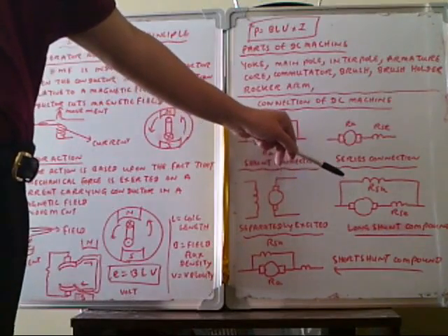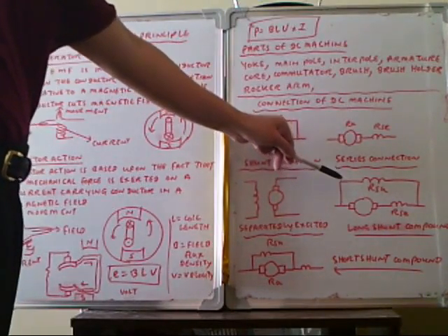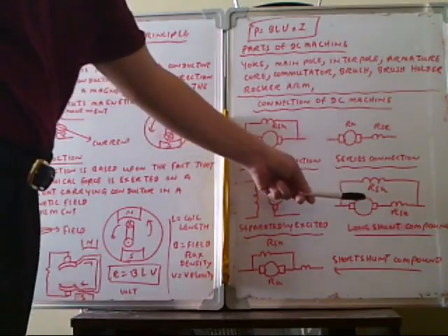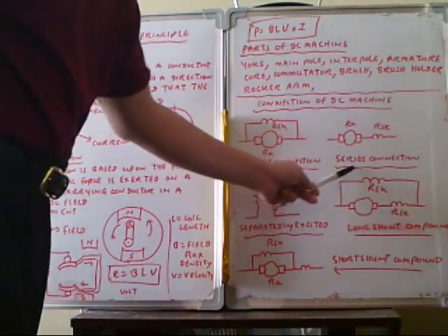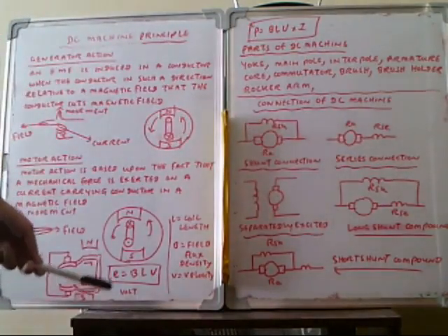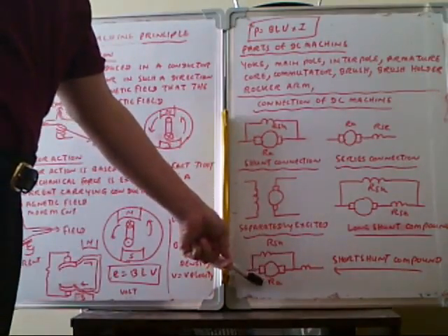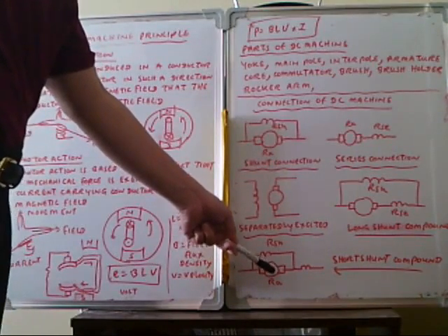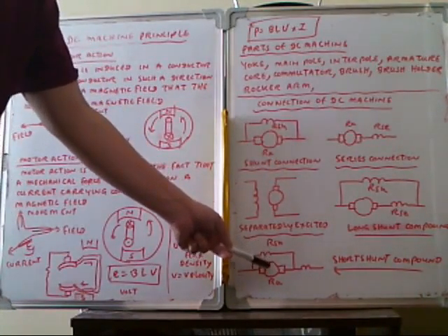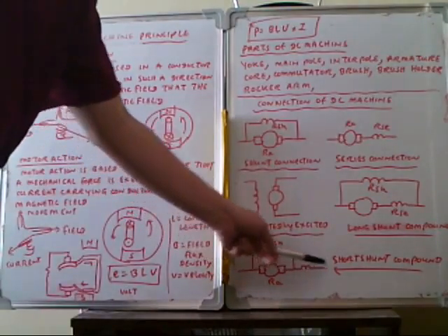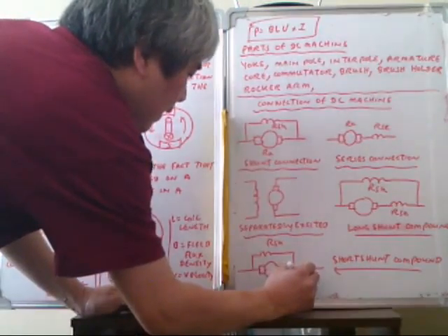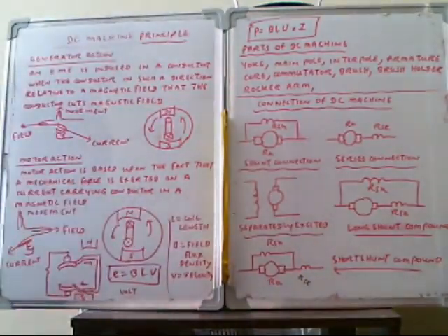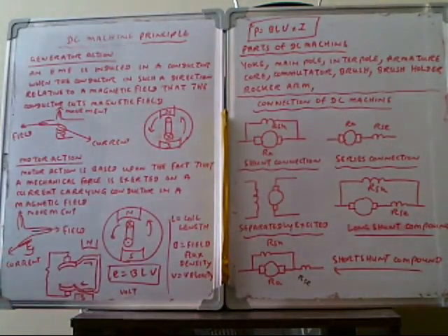This is the long-shunt compound generator. It consists of the armature, series field, and shunt field. The armature and series field are connected in series, and this combination is connected in parallel with the shunt field. For the short-shunt compound generator, the shunt field is connected in parallel with the armature only, and the series field is connected in series with the whole combination of the armature and shunt field.